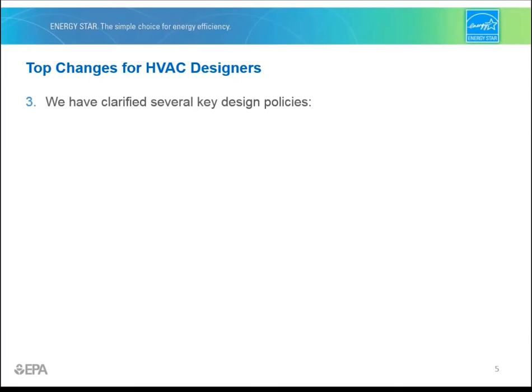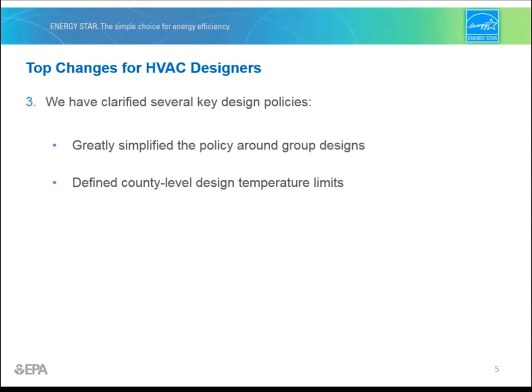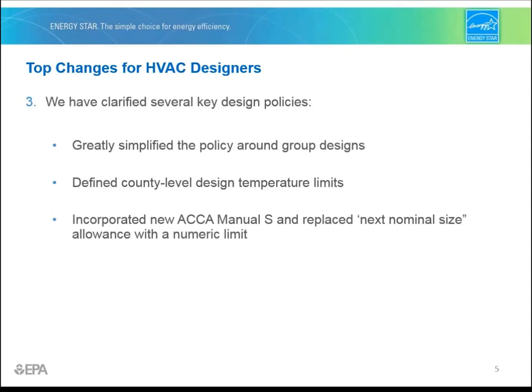And number three, we have clarified several key design policies. We greatly simplified the policy around group designs, meaning a plan that is intended to be built with potentially different elevations, options, orientations, or locations. We've defined outdoor design temperature limits for every county instead of requiring the designer to look up the closest weather station for each home. And for system sizing, we've incorporated the latest version of ACCA Manual S, removed the next nominal size allowance, and replaced it with a numeric limit. These three changes should make it easier to understand and meet our program's requirements.